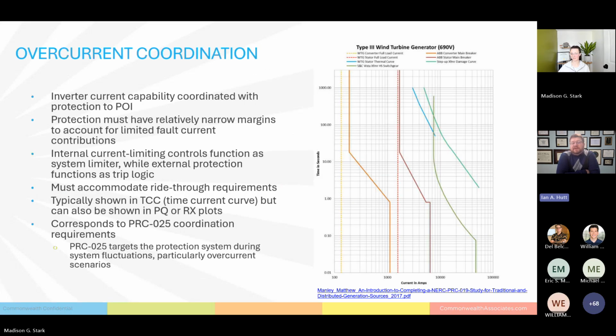So how do you read the last time current curve? Great question. For a little more explanation on what we're looking at here, this is a type 3 wind turbine generator. A type 3 wind turbine generator outputs some power via a converter and some power via a traditional generator type connection. That's why you have 2 full load currents and 2 protection curves.